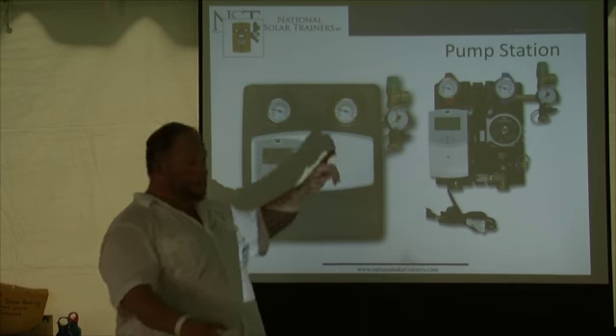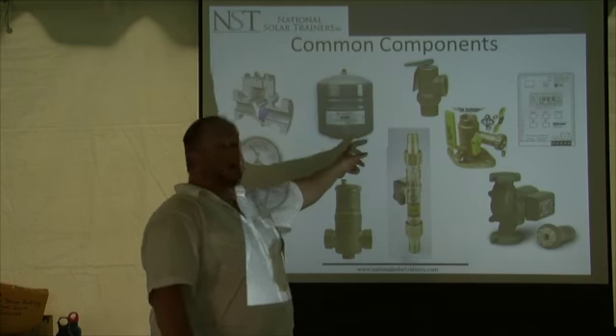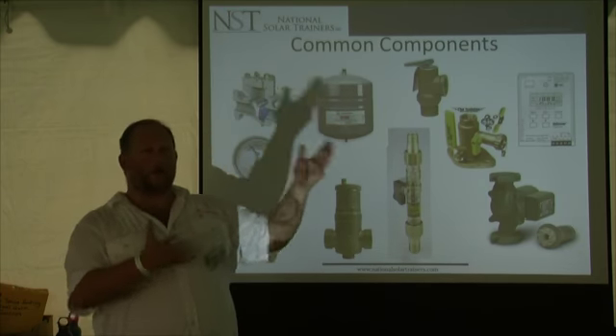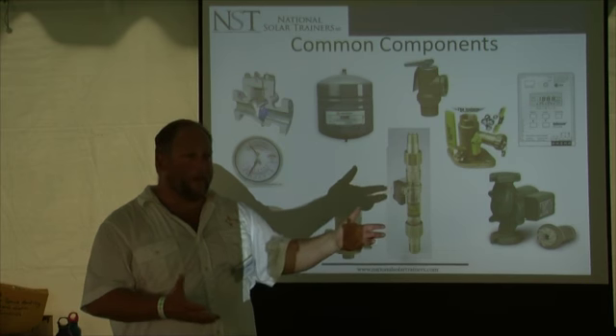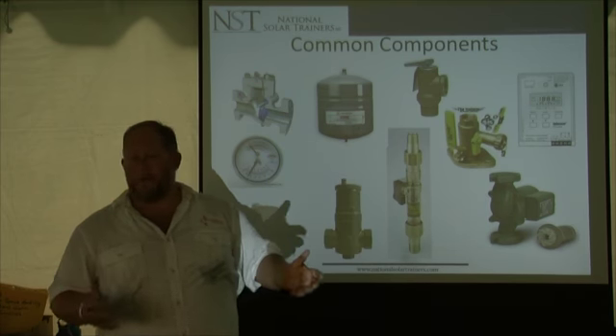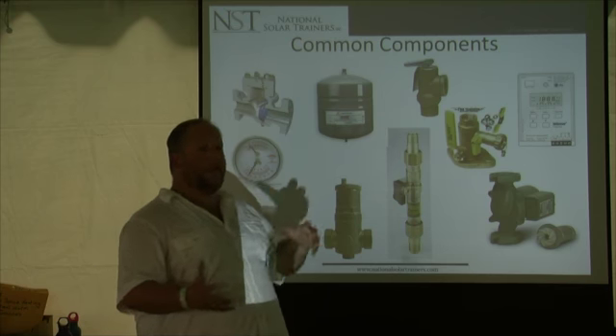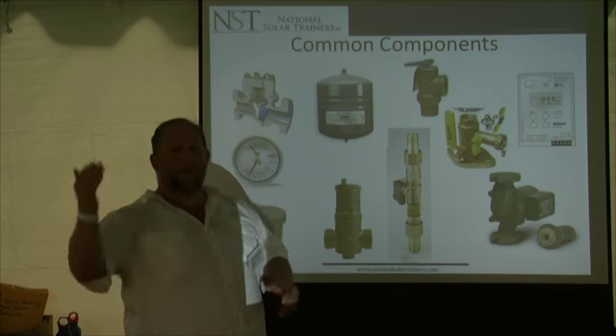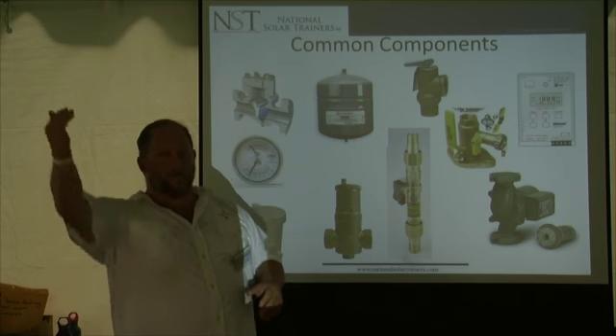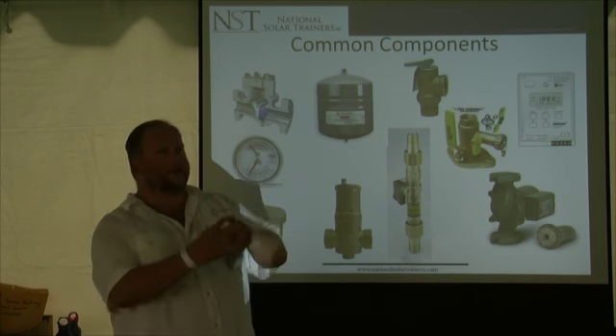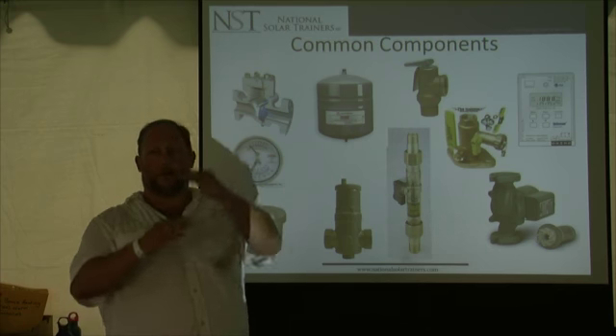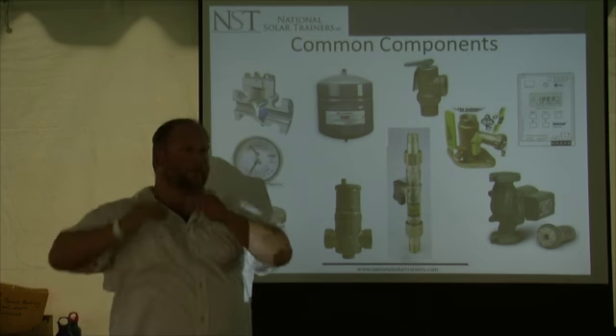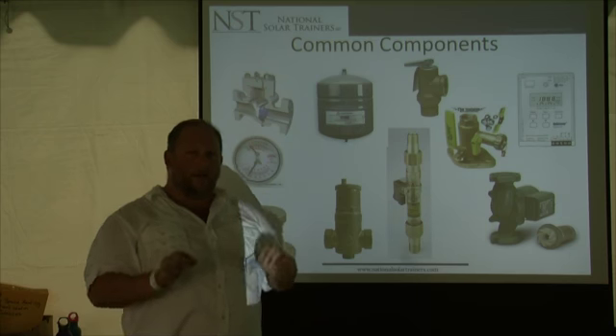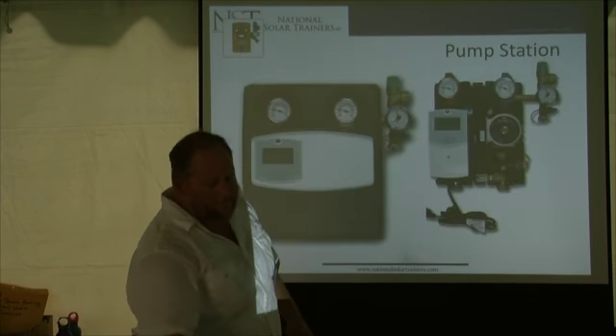But if my expansion tank is too small, then the collectors don't empty properly. Then I burn my glycol. If the expansion tank's in the wrong spot, I burn my pump out because I got that hot fluid moving down. It's got to go in the expansion tank first. That's why I put it between the pump and the collectors. All right? So there's a lot of little details that make a big difference.